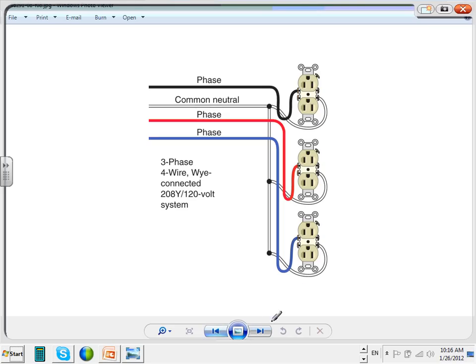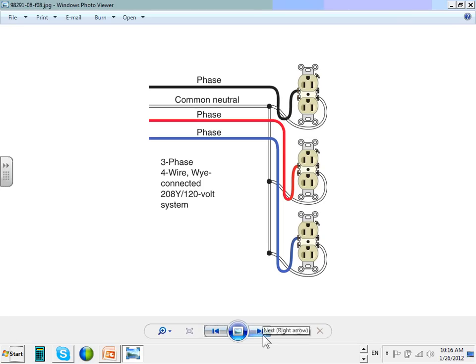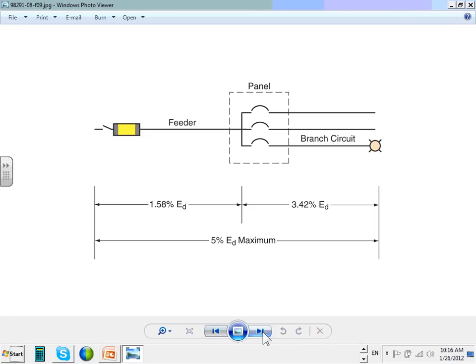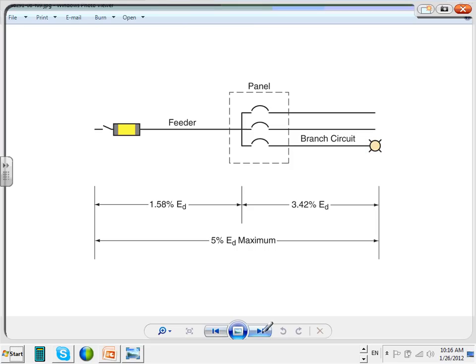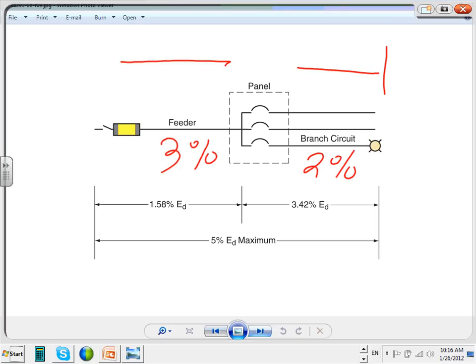Okay, so let me take you guys quickly here. All right, so moving a little bit into the voltage drop, guys. For both feeders and branch circuits, the code says you can have 3% voltage drop here, 2% voltage drop here, for no more than 5% total. These are NEC recommendations for no more than 5%.